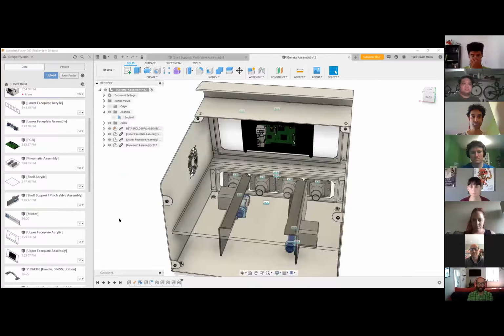Yeah, thanks for sharing that, because that might change my decision a little bit. I'm not too worried about the vibration test, but the shock, 30 Gs is a lot. And especially with connections, I'd hope that our tubing connections are pretty good. Yeah, I wouldn't worry about the tubing connections. But I'd be worried if we moved something enough that a wire got pinched or something fell out, that would be a problem. Yeah, it probably means that we just want to make sure that everything is secure, that we don't have something that flops, right?